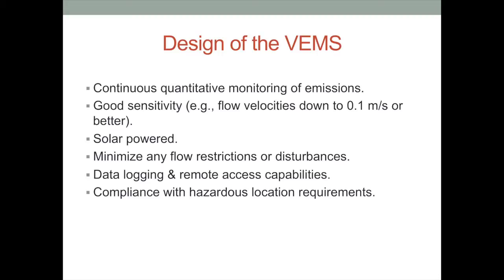The underground tank panel is being powered using a solar panel, while the above-ground tank will use actual site power. We've used clamp-on ultrasonic flow meters on the underground tank, and on the above-ground tank we're going to use a flow cell similar to the ones used for casing gas venting. By wetting the transmitters to the flow, we get better signal response from those transmitters. So we're doing that on the current tank.